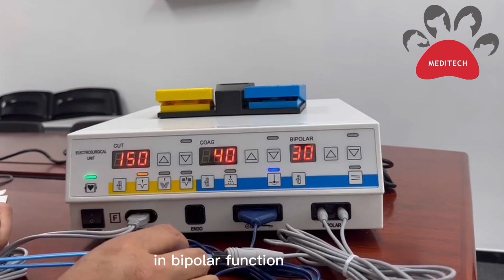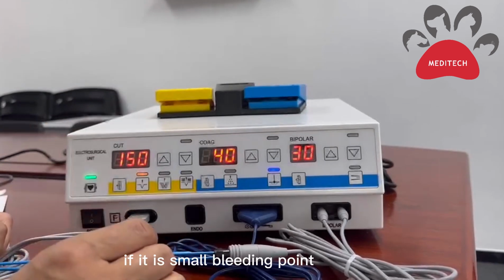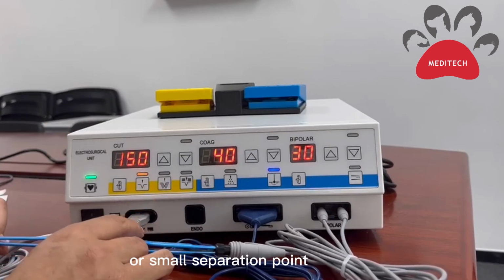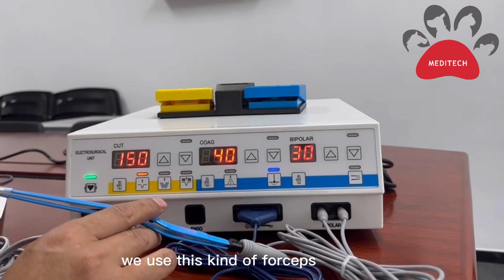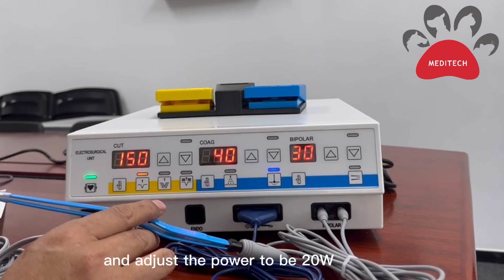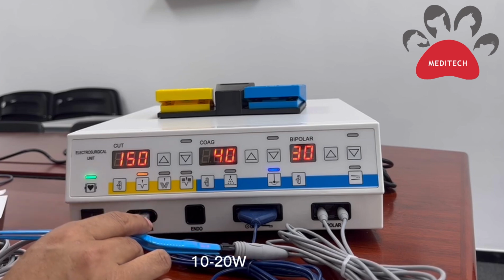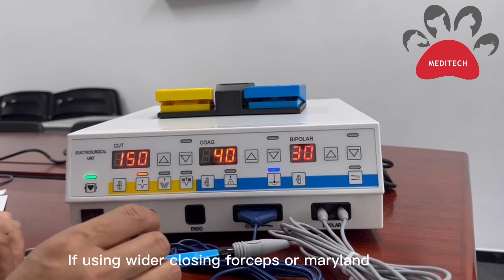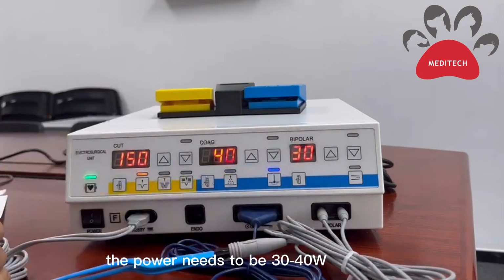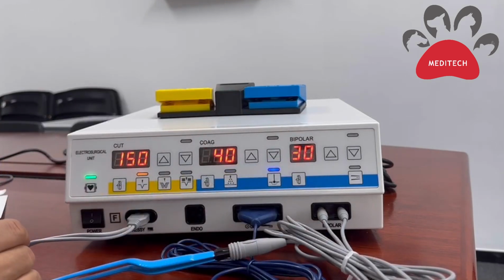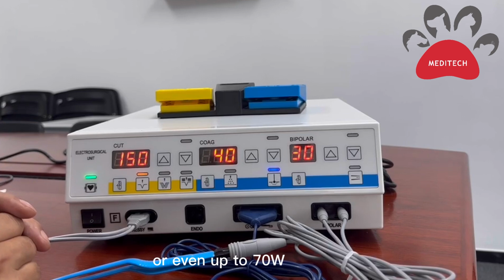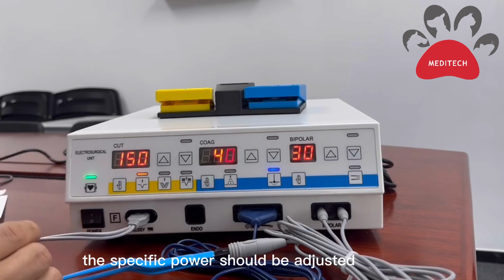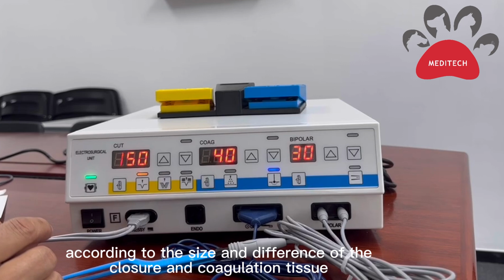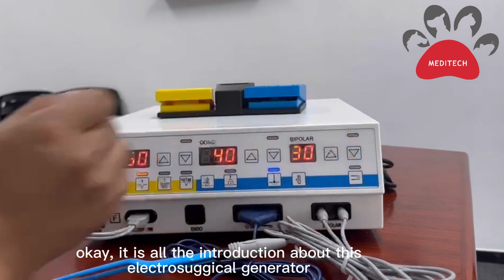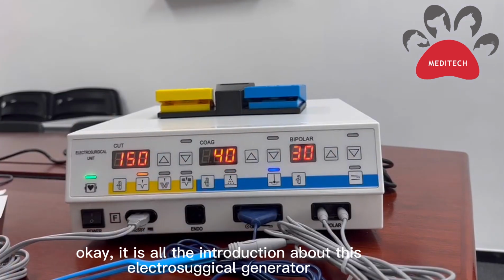In bipolar function, if it is a small bleeding point or small separation point, we use this kind of forceps and adjust the power to 10 to 20 watts. If using wider closing forceps or Maryland, the power needs to be 30 to 40 watts, or even up to 70 watts. The specific power should be adjusted according to the size and difference of the closure and coagulation tissue. Okay, that is all the introduction about this electrosurgical generator.